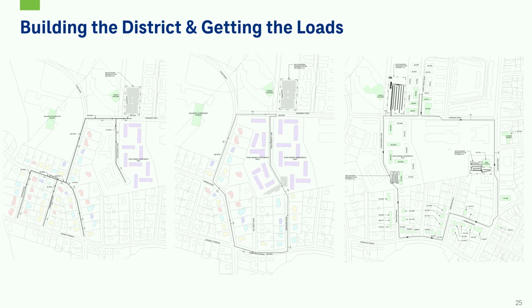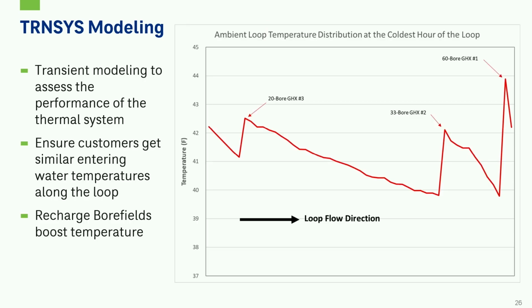And so as we were finalizing who is connected, we really took a close look at those building energy loads, put together the hourly load data for each building, and then we were able to finalize the number of boreholes required at each of those bore fields using GLD. And then we were able to input that into TRNSYS to assess the performance of the thermal system.